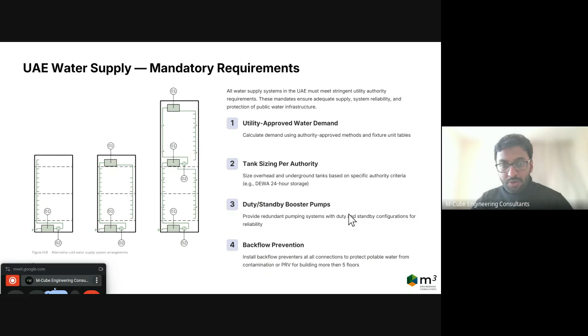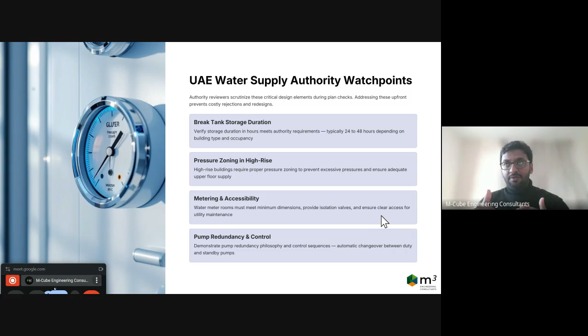Regarding water supply authority watch points, again it relates to the tank storage duration, whether 12, 24, or 48 hours for your underground water tank. For healthcare facilities, we generally estimate 2 to 3 days of water storage, so this depends on the type of project. Also consider pressure zoning for buildings, whether low rise, high rise, or super high rise, ensuring proper zoning, metering, accessibility, and identified water meter rooms. Ensure pump redundancy, with duty and standby pumps for both transfer and booster pumps.